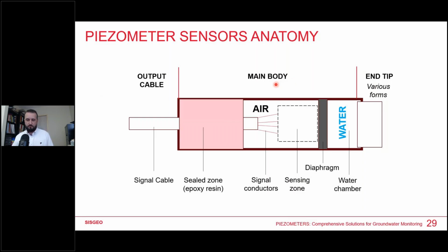The main body contains very important parts inside. First, the end tip is closing the system between the environment and the main body. Inside this chamber, you just have water. At the beginning, when you get your supply, it's air, but you have to fill it with water. This chamber is separated from the main body electrical part by a diaphragm. This diaphragm is a very important piece that will deform. Whenever the water exerts a pressure on this diaphragm, it will deform. Then you have the sensing zone measuring this deformation.